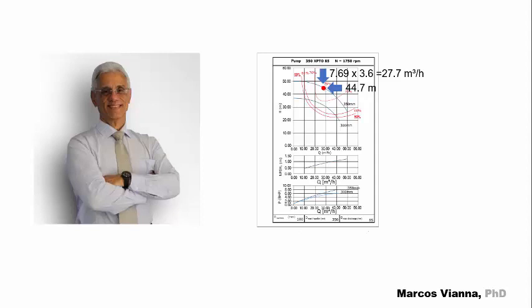The flow value has to be transformed from liters per second to cubic meters per hour. It's easy. You just have to multiply it by 3.6. This allows us to find the BHP and the required NPSH in the same chart. But this is a topic for another video.